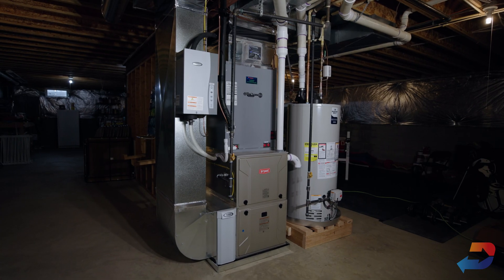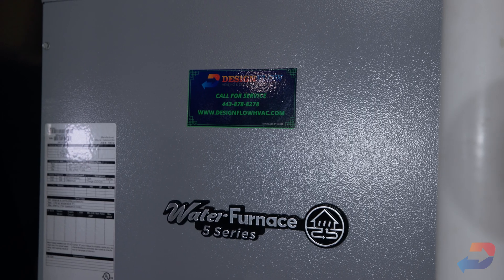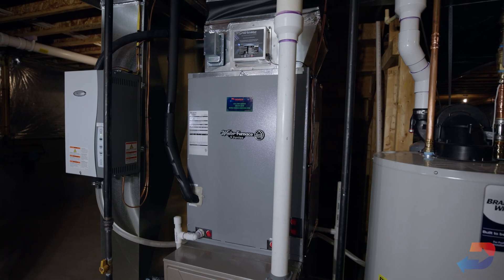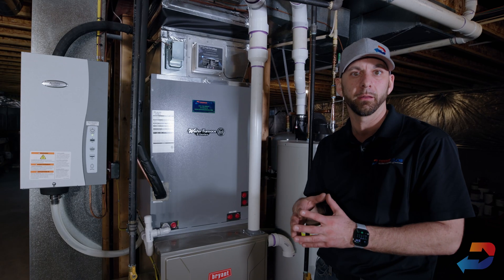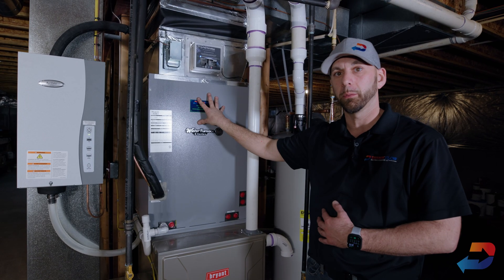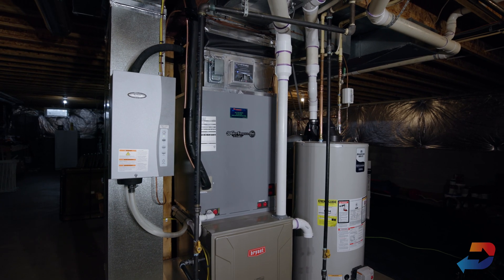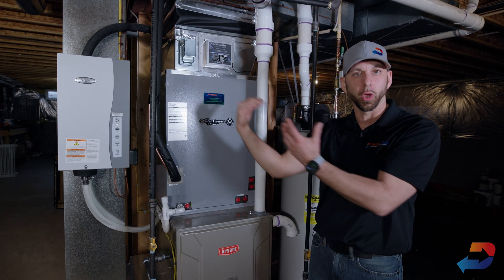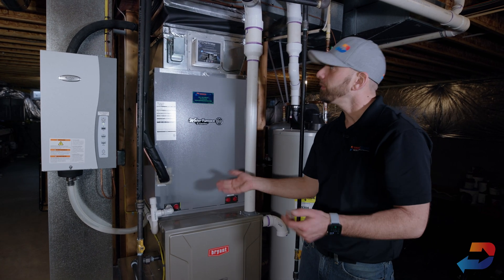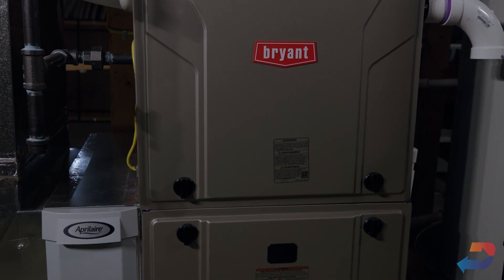With this system — what we call a hybrid heat pump — it is a WaterFurnace 5-series geothermal system, but still a heat pump paired with a natural gas furnace. Because geothermal is so efficient, with a normal hybrid heat pump we typically set the changeover around 35 degrees, but this one we can set to 20 degrees. In fact, running historical data, when it went down to 15 degrees outside, it still did not run the fossil fuel furnace. It was more budget-friendly up front because we didn't have the electrical infrastructure to go all electric — the infrastructure was already here for the gas. And if something did happen, this gas furnace can take the entire heating load of the home, so they will never be without.